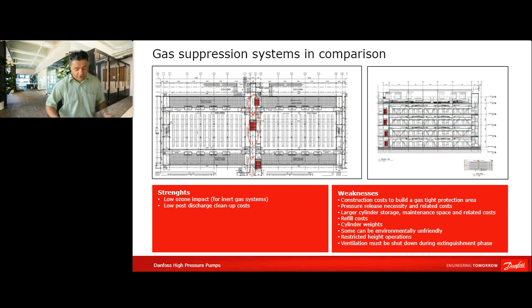And for sure, one of the major disadvantages that we see is that in many concepts of gas extinguishing systems, you have to shut down the ventilation in order not to suck out the gas from the extinguishing rooms, and this is not necessary with the high pressure water mist system. So you can feel free to let the ventilation run while you are extinguishing any area in that building.